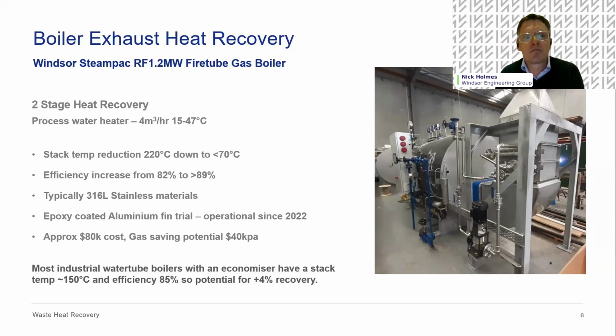And with the reasonably high water flow, we got that water temperature up to 47 degrees. There's always a trade-off: if you want to get a higher water temperature, it would reduce the water flow rate, and you'd probably need to put more heating surface in there as your pinch point gets closer. So here we've got the disparity between the 70 degrees outlet temperature and 47 of the water. If you're trying to get a higher water temperature, you just need more heating surface to get there.